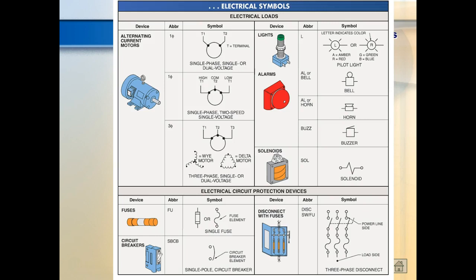Now when we get into motors, we'll talk a little bit about delta Y. The symbol itself does not identify whether it's a delta motor or a Y motor, unless they draw the little symbol right here. If it's just a delta Y motor, it really doesn't make any difference. It's when you get into multi-voltage motors where delta Y makes a difference. Normally they'll start the motor in Y and then switch over to delta when it gets up to a certain speed.